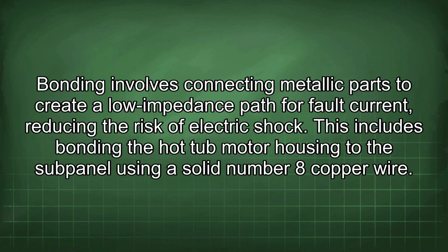Bonding involves connecting metallic parts to create a low impedance path for fault current, reducing the risk of electric shock. This includes bonding the hot tub motor housing to the subpanel using a solid number 8 copper wire.